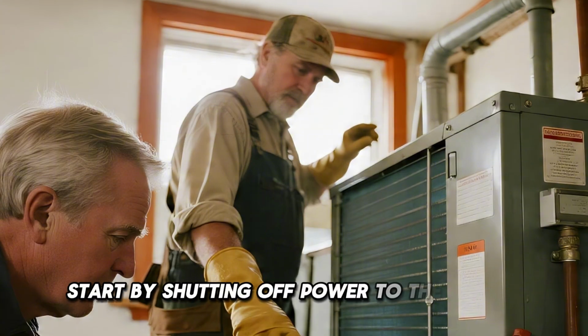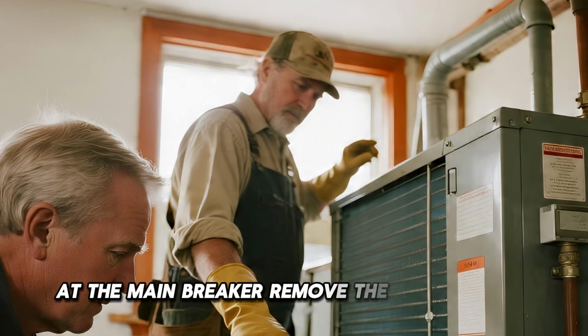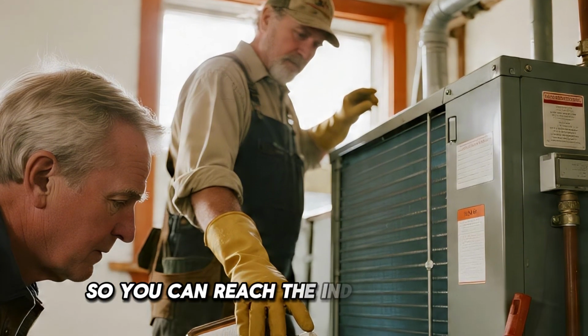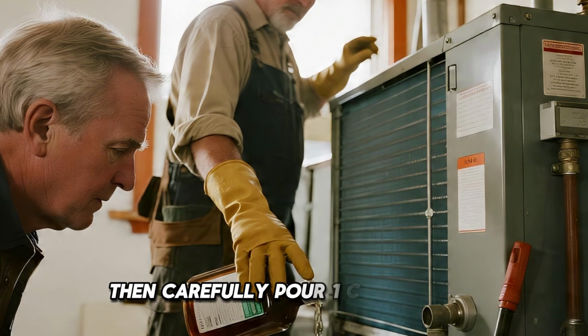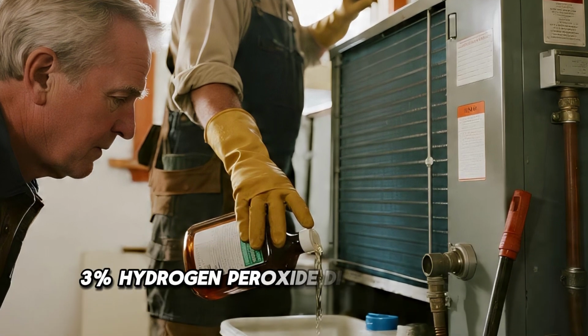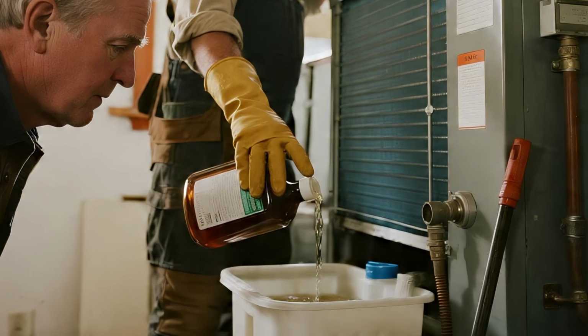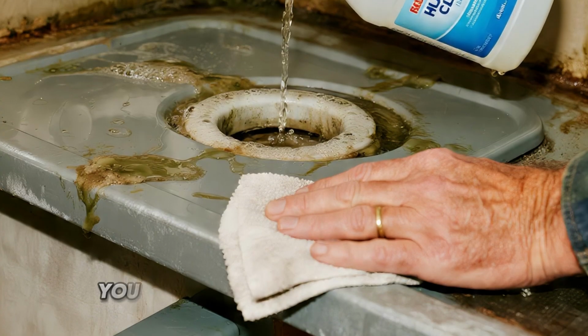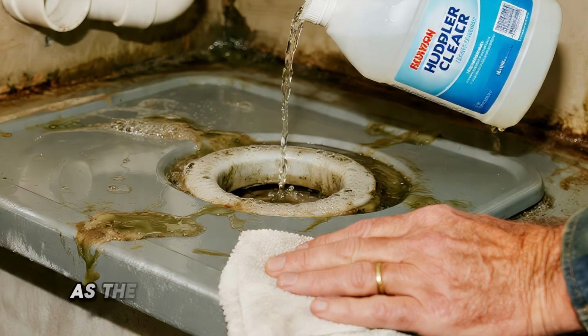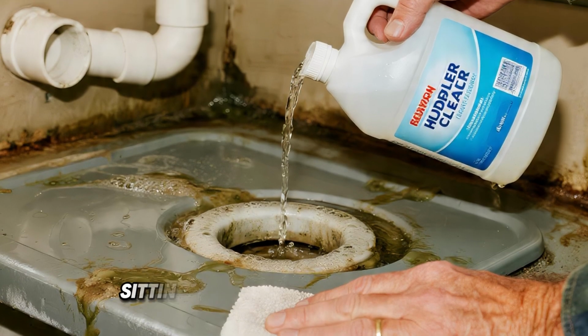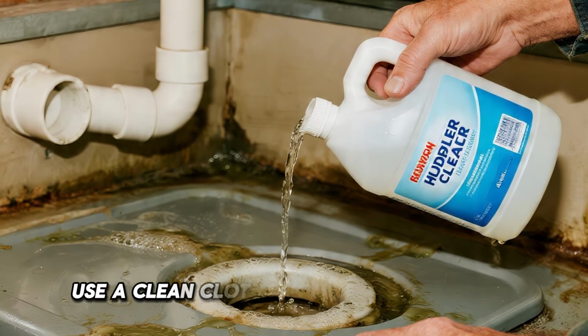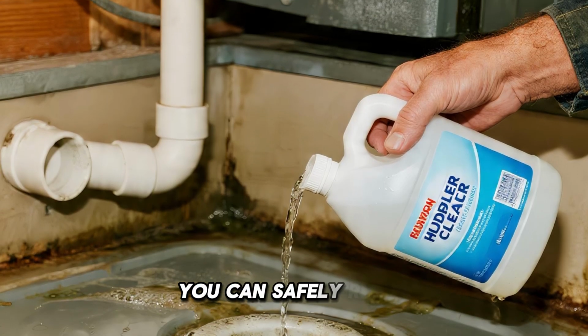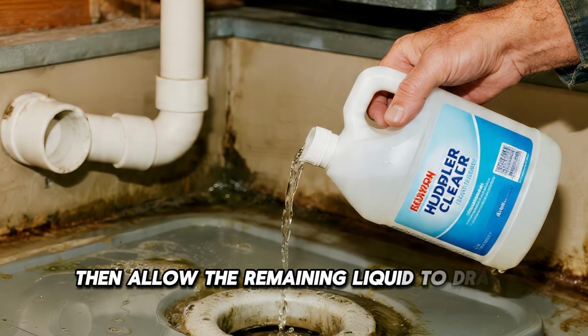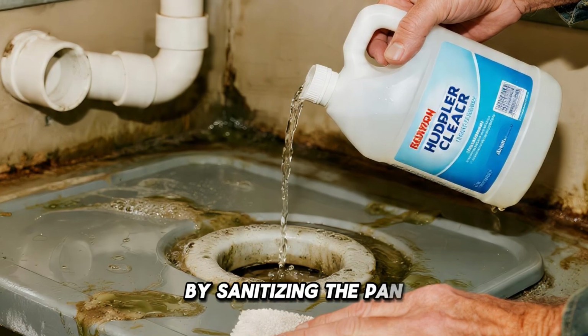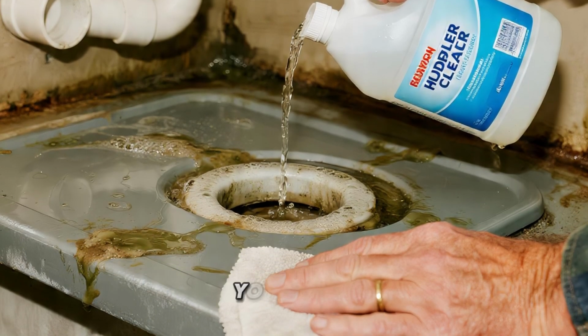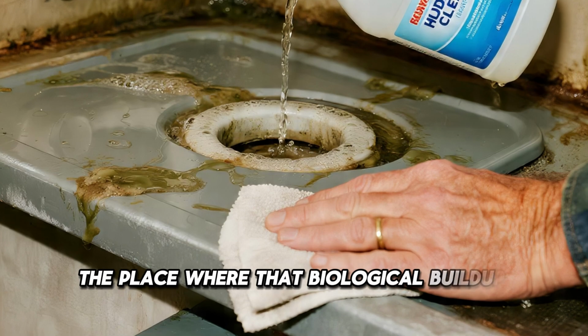Start by shutting off power to the system at the main breaker. Remove the access panel so you can reach the indoor coil area. Then carefully pour 1 cup of fresh 3% hydrogen peroxide directly into the drain pan. Let it sit for about 10 minutes. You should hear fizzing and bubbling as the peroxide works against the biofilm sitting on the bottom of the pan. Use a clean cloth to wipe away anything you can safely reach. Then allow the remaining liquid to drain naturally. By sanitizing the pan before dealing with the downstream line, you attack the place where that biological buildup begins.